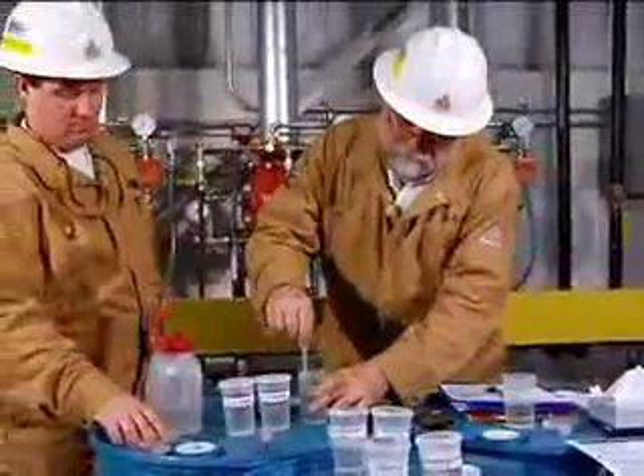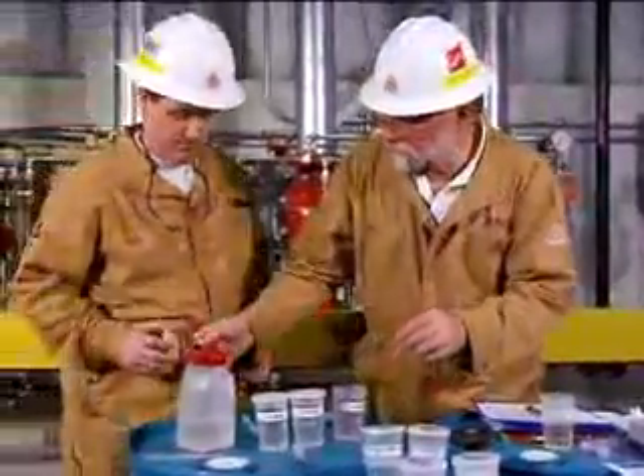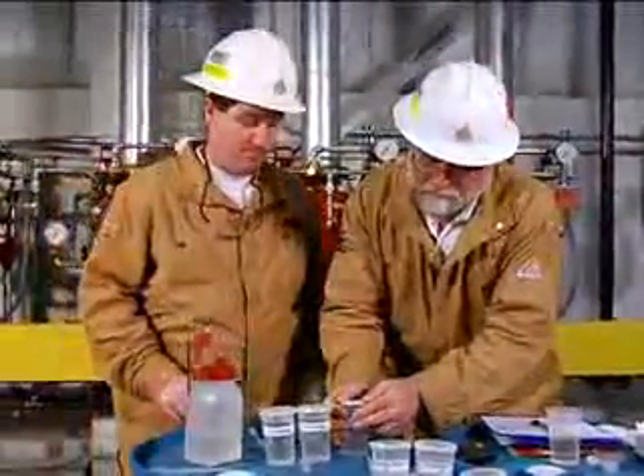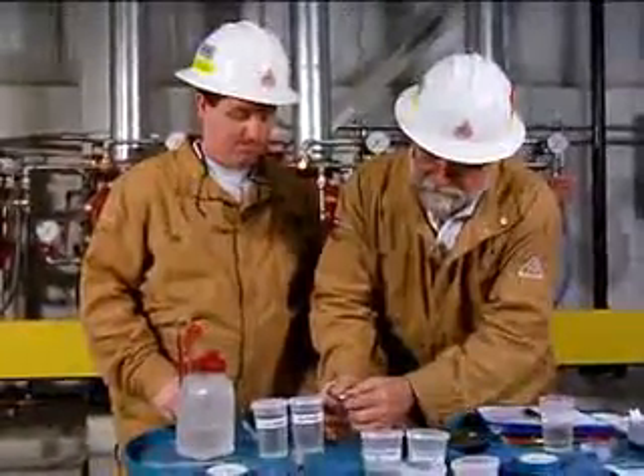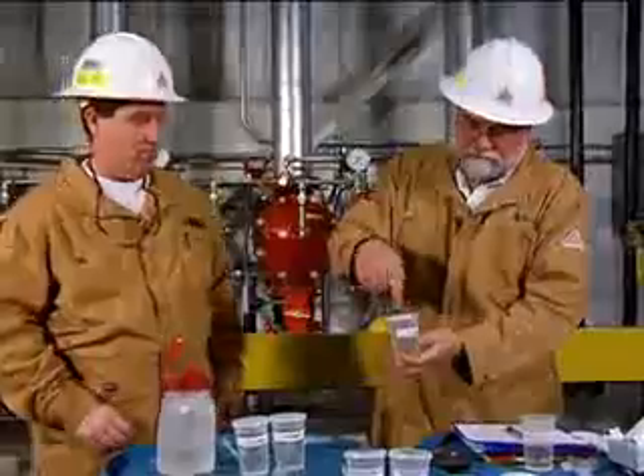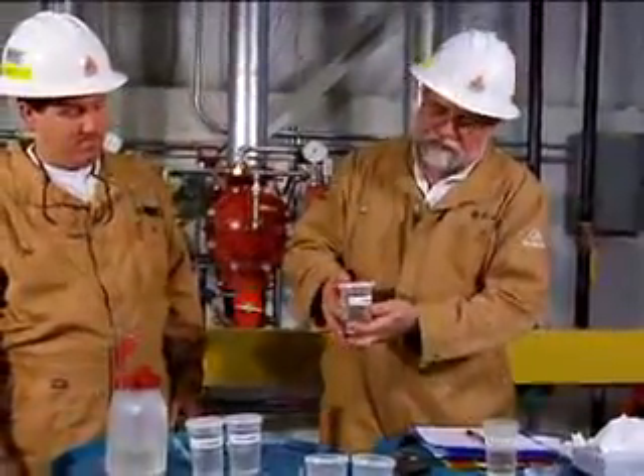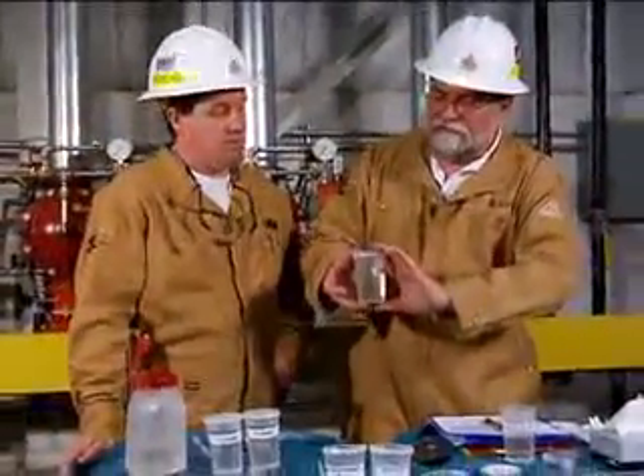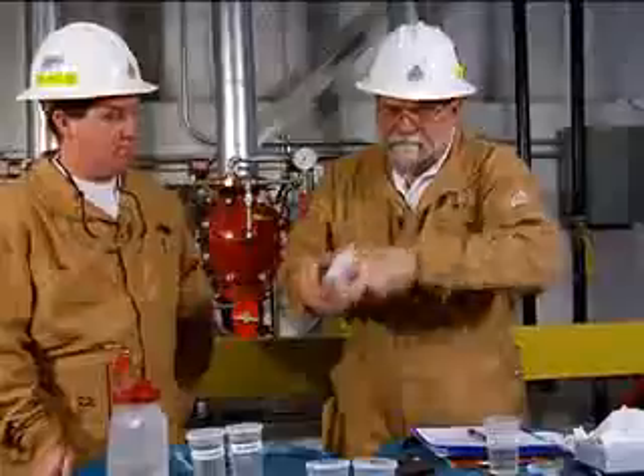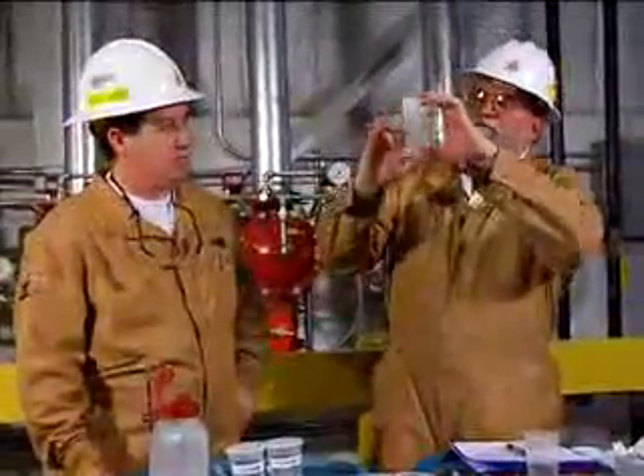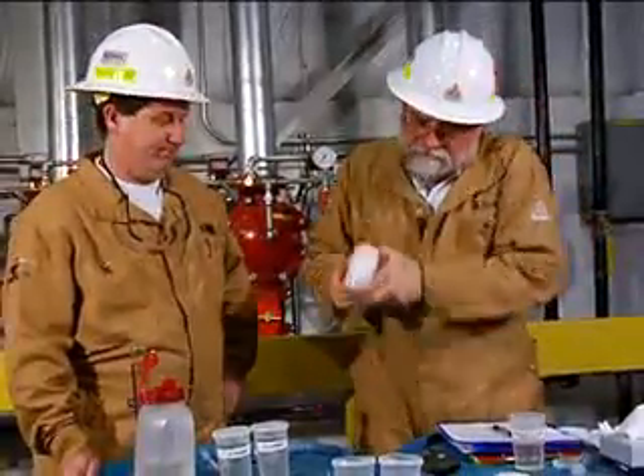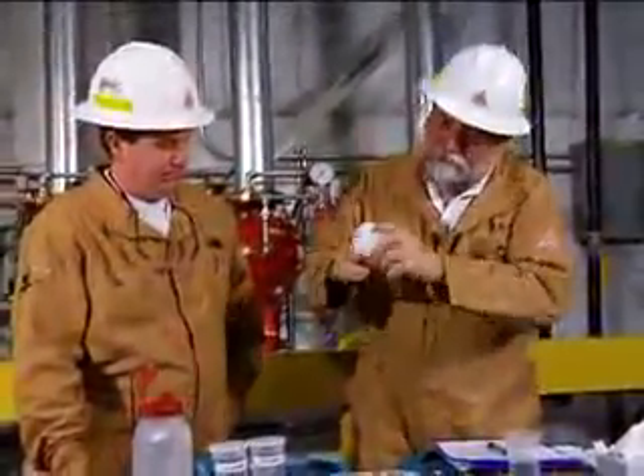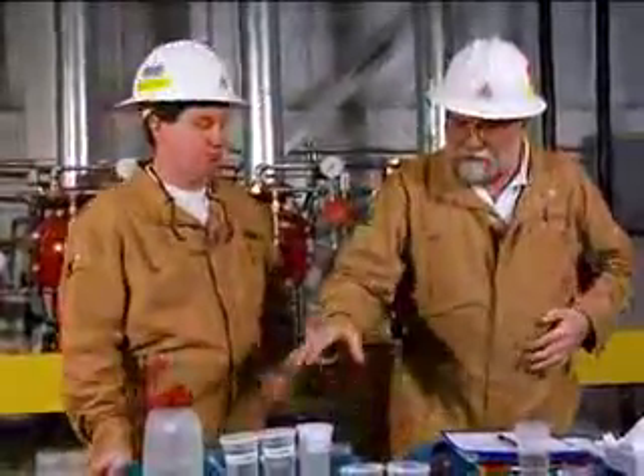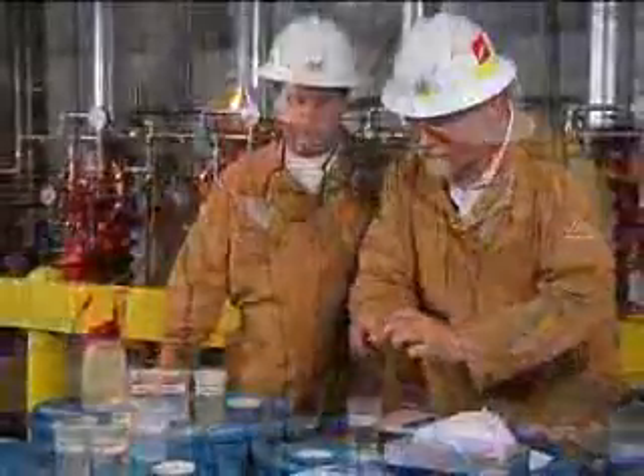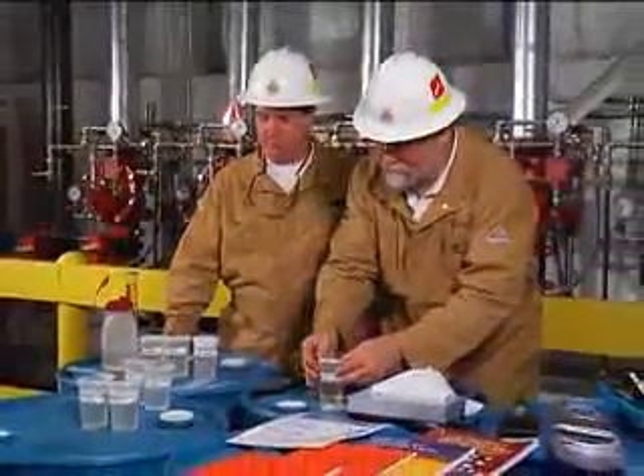And we'll mix. Now, with some types of foam concentrate, such as 3% AFFF or JetX high expansion foam concentrate, you can mix them very easily just by stirring them. With some types of foam concentrates, particularly the alcohol-resistant foam concentrates, you need to physically mix them, and then inspect them to make sure that you have all the concentrate mixed into the solution. And again, with this type of foam concentrate, it goes into solution very quickly. We don't have to do that. But again, with an alcohol-resistant foam, we would.